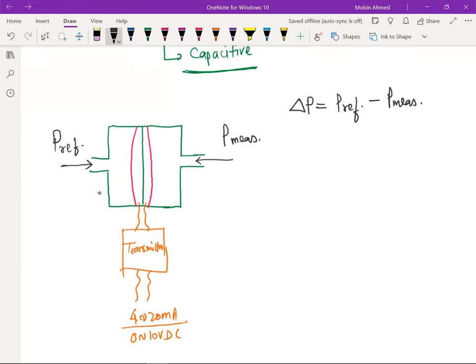So this is how it gives the output, a differential pressure output. Generally, this P reference is always a constant pressure. It is not going to change. It never changes because it is a reference. Reference should not change, remember. And the P measured, this is a variable one.